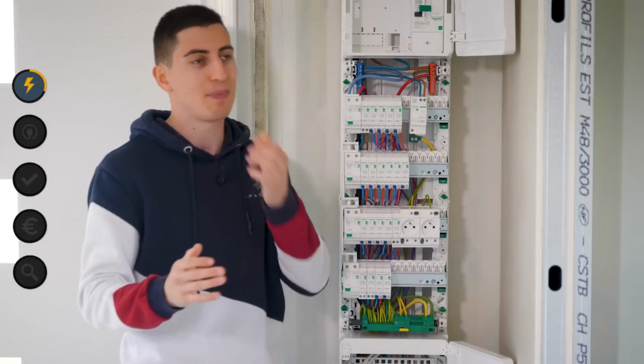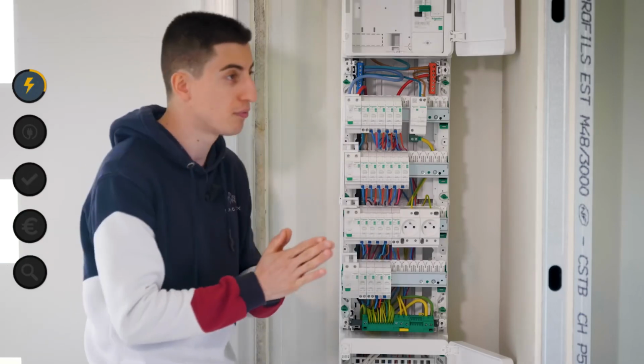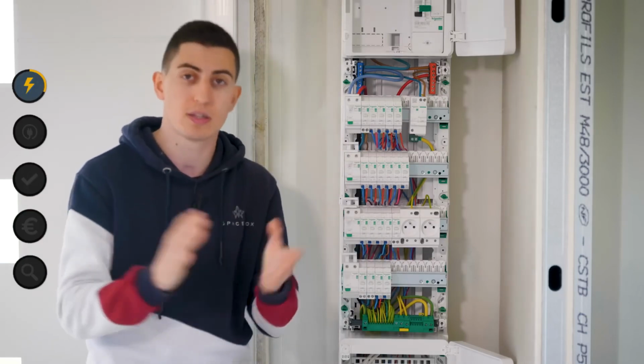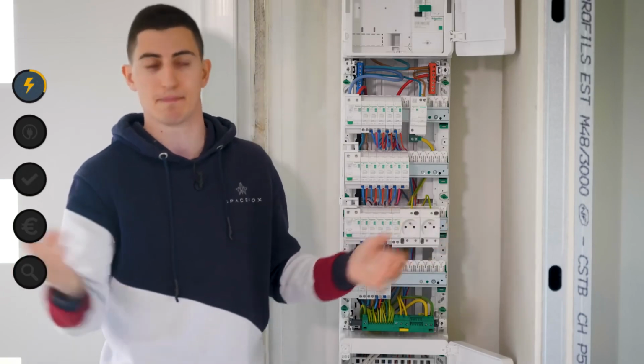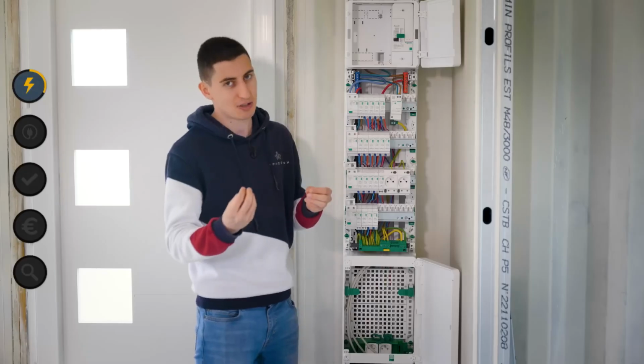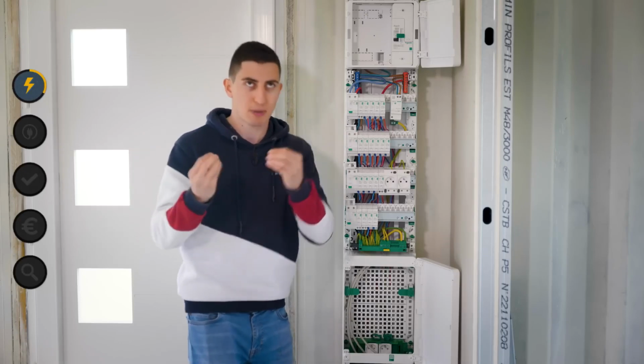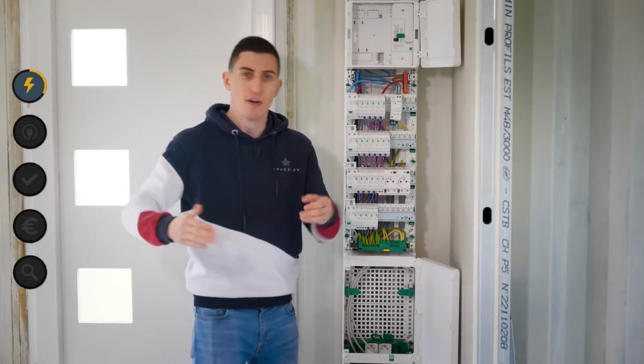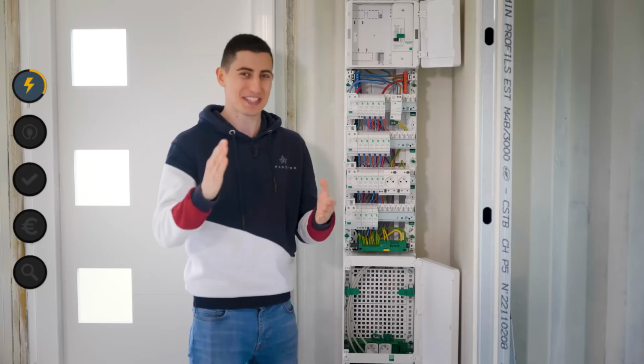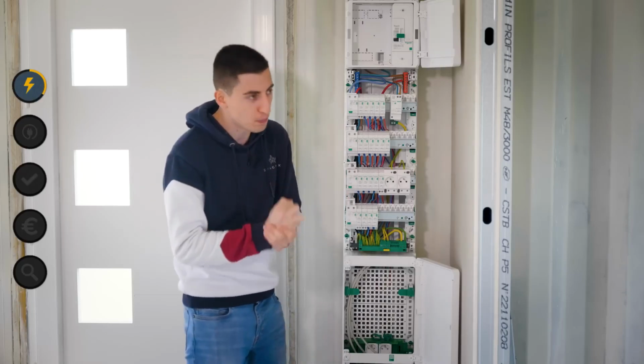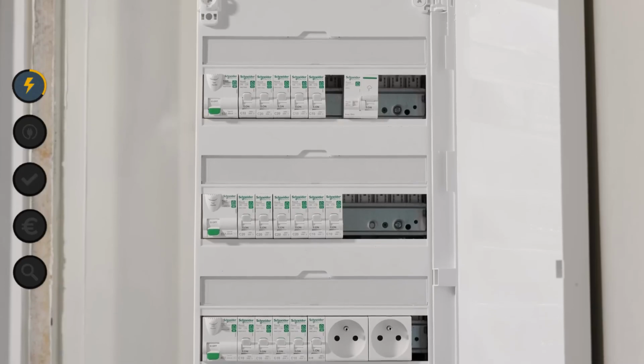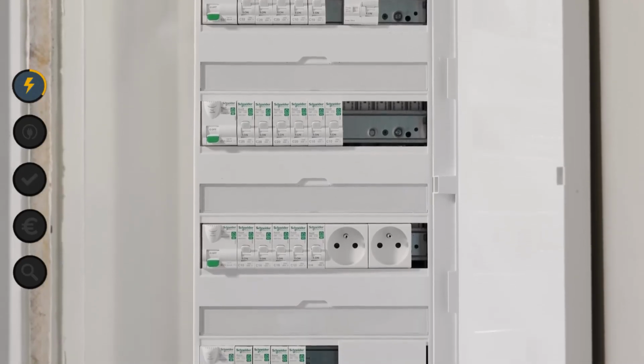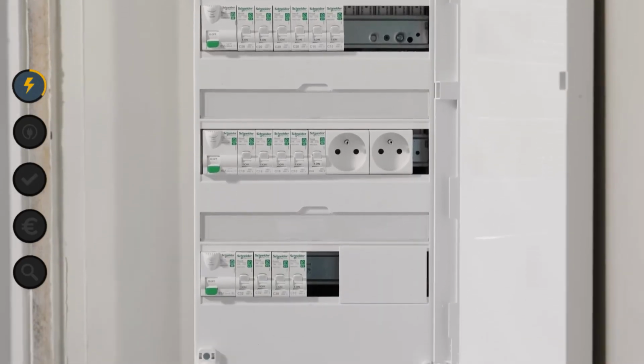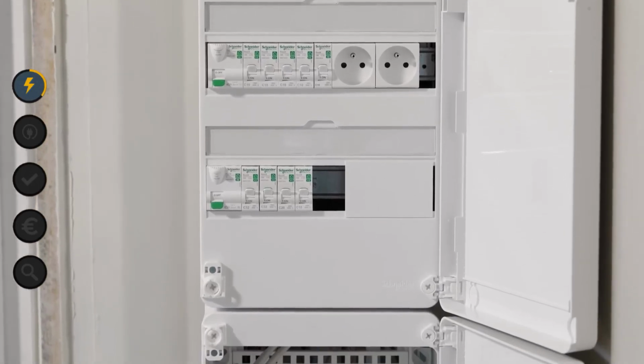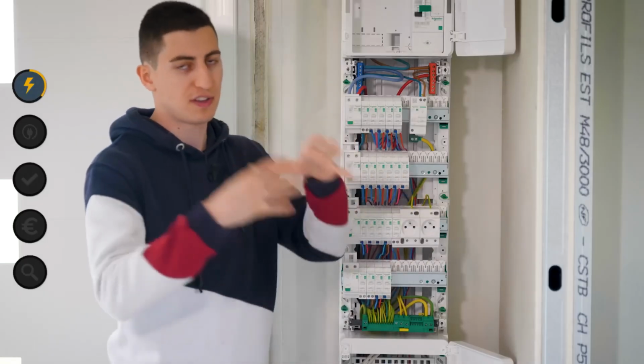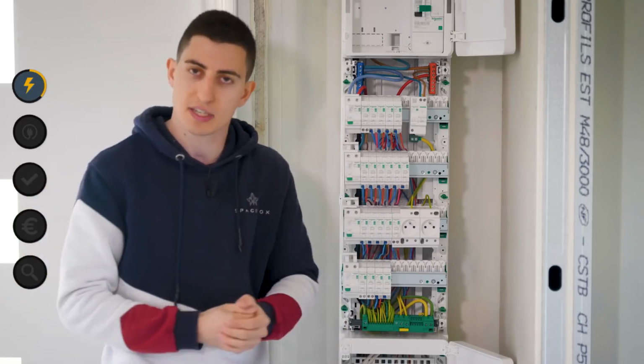Be careful though, because even if, for example, you have an oven that only uses 3,000 watts and you think 16 amps won't trip the breaker, the NF C 15-100 still advises you to use 20 amps. I think it's in case the next occupant of the house has a more powerful oven than yours; it still needs to be adaptable to all uses. So you can calculate the power you need, but also pay attention to the recommendations of the NF C 15-100.